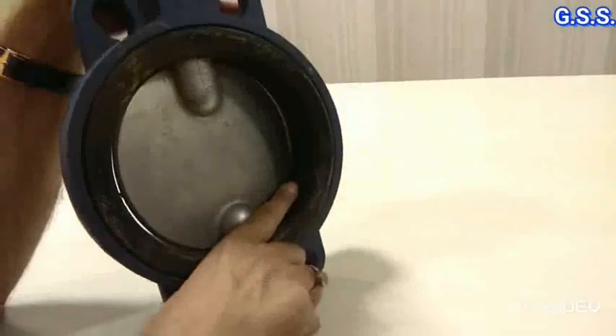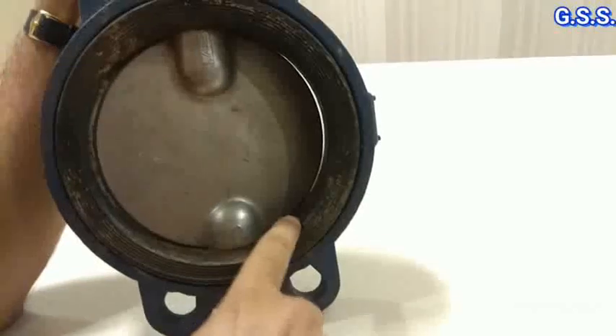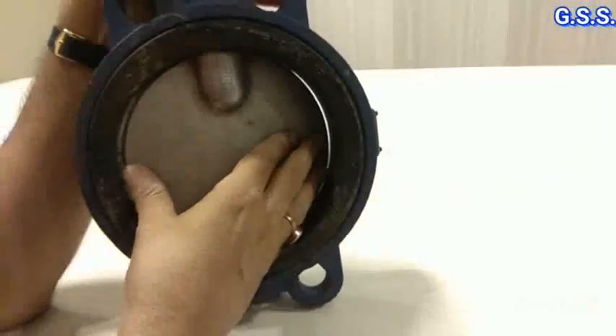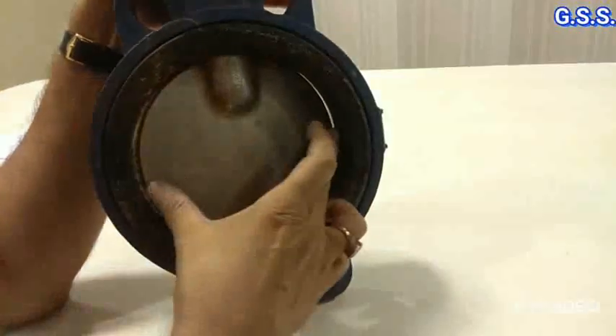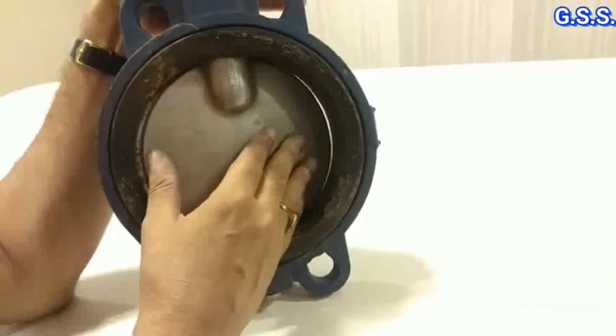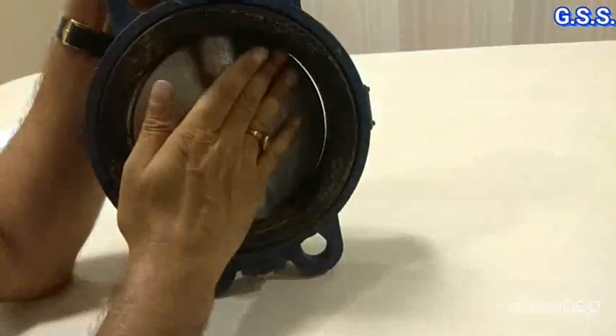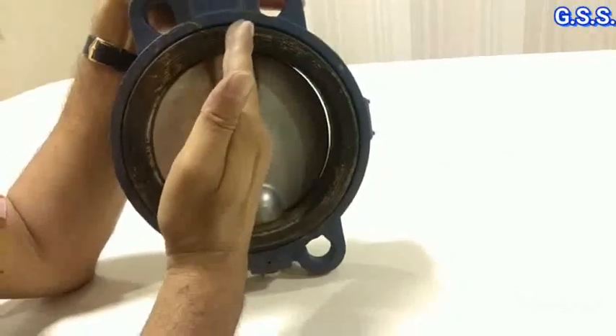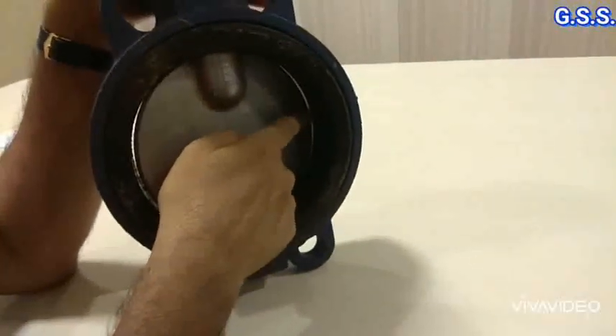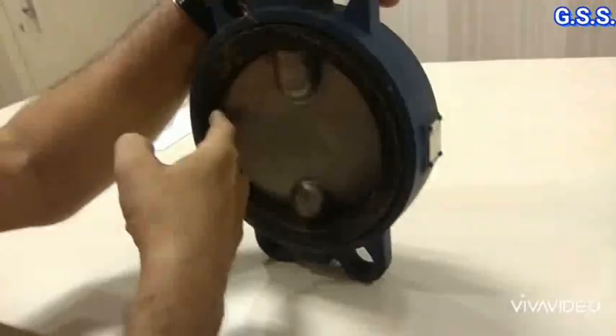Now this body seat actually tapered from center to this side and center to that side. That's why when this valve will be fully closed then this disc will press the body seat and we will get leak tightness. Now the valve is in almost closed condition. When it will be opened it will be rotated 90 degree like this. And when it will be closed it will be closed like this and this surface will press over this seat and this surface will press at the center of the seat.